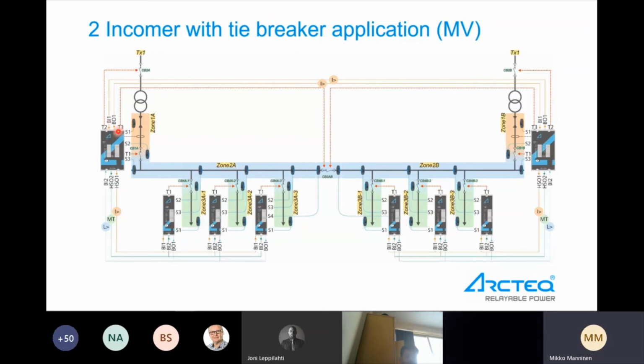If we have current here, the tie breaker is closed, and we have flash over here, because the current is shared between left and right, we will still get the current from the left side. Flash will be seen on the right side, and this master unit will know what to do, and it will open the tie breaker here and the incomer breaker here.